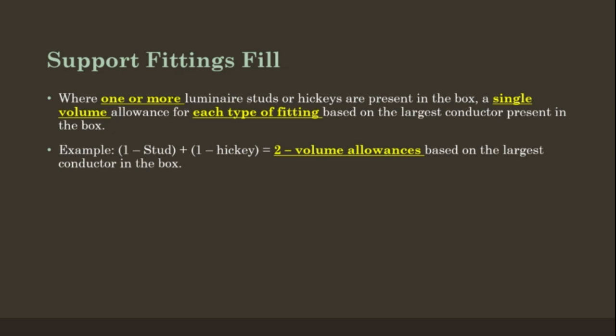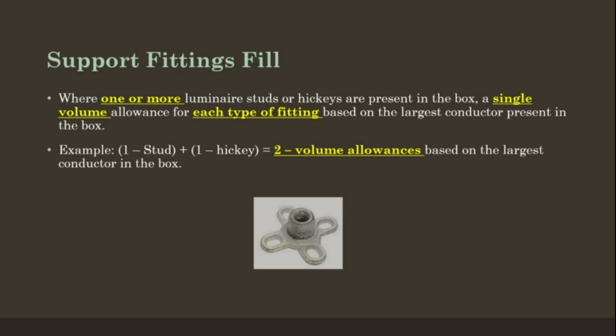Example: One stud plus one hickey would equal two volume allowances based on the largest conductor in the box.